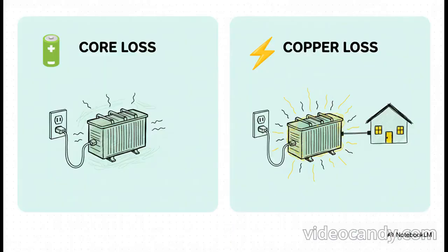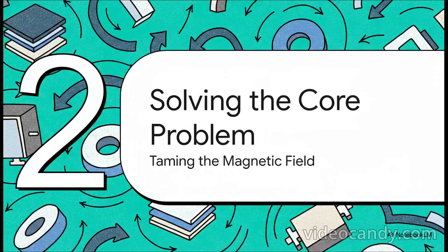What's really interesting is how the problem splits in two. On one side, you've got core loss, the easiest way to think about this is like a car that's idling, a constant drain happening 24/7 as long as the transformer is energized. On the other side, you've got copper loss, which is all about performance. It only shows up when you're actually using the power, and it gets worse the harder that transformer has to work. So let's tackle that first problem, the constant nagging core loss.